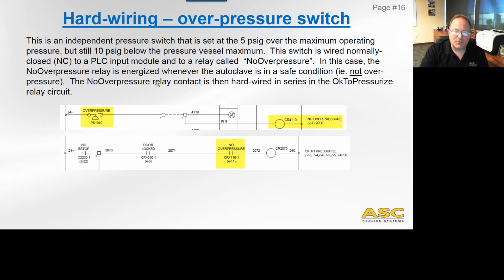The no overpressure relay contact is then hardwired in the OK to pressurize relay. So what you see here is because OK to pressurize is also a permissive for auto enable, you can see that when we get an overpressure condition, it will also shut off heating. And the reason we want to do that is because adding additional heat will pressurize the autoclave just by the expansion of the gas. Okay.